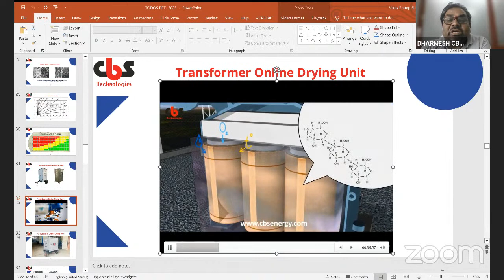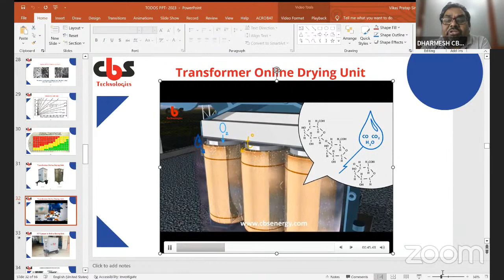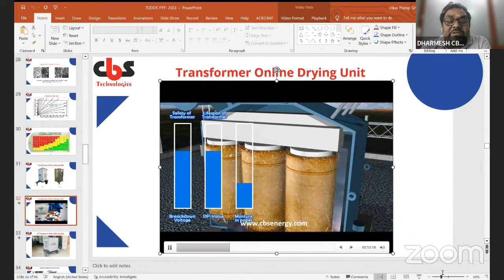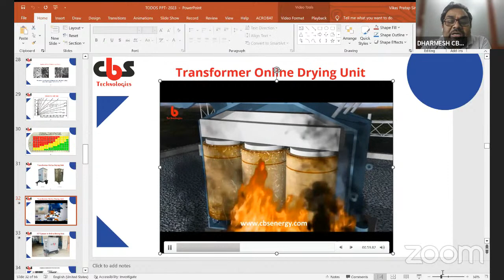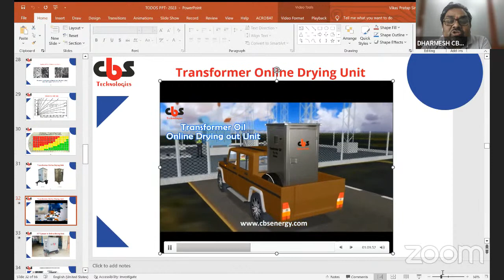See how this chemical reaction takes place after ingress of water and moisture. The byproducts are carbon monoxide, carbon dioxide, and water content. All these increase, breakdown voltage decreases, the DP value decreases, and ultimately fire can take place, and the whole system collapses.